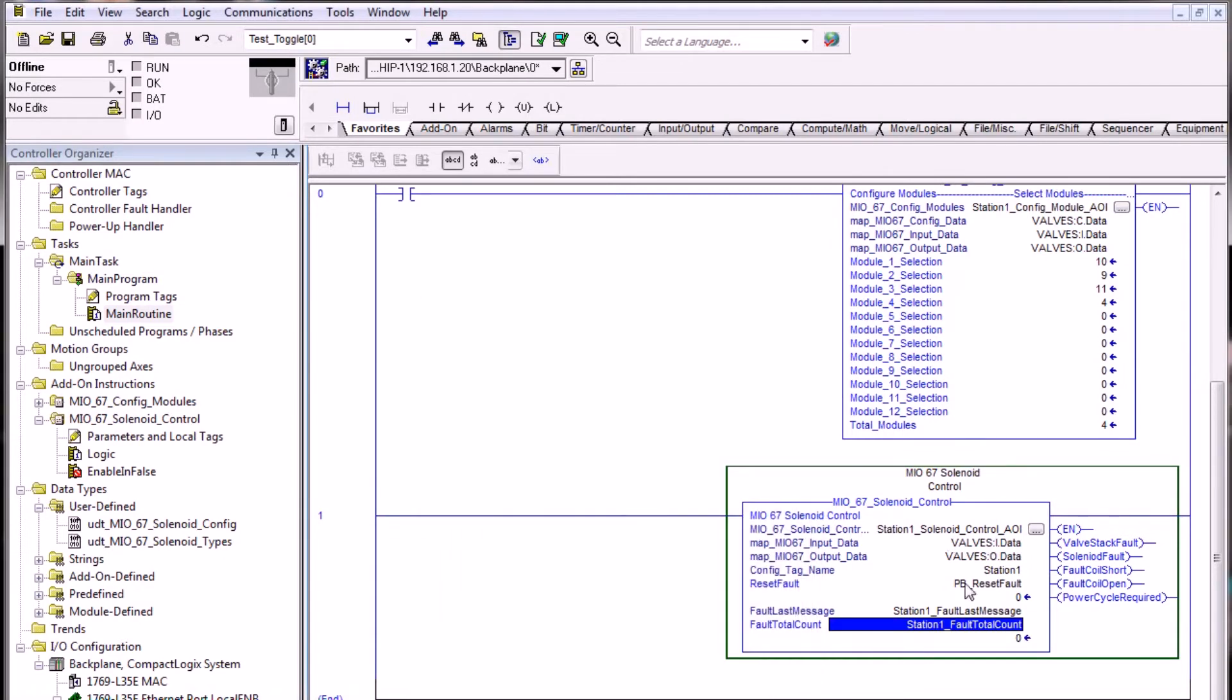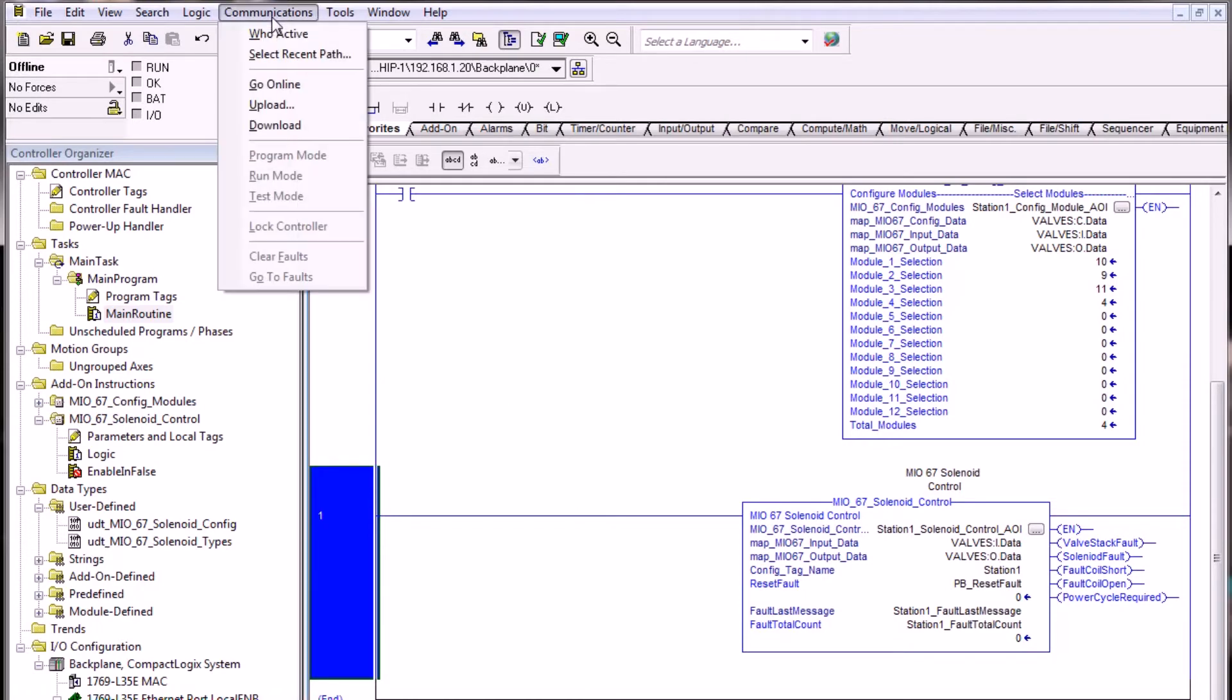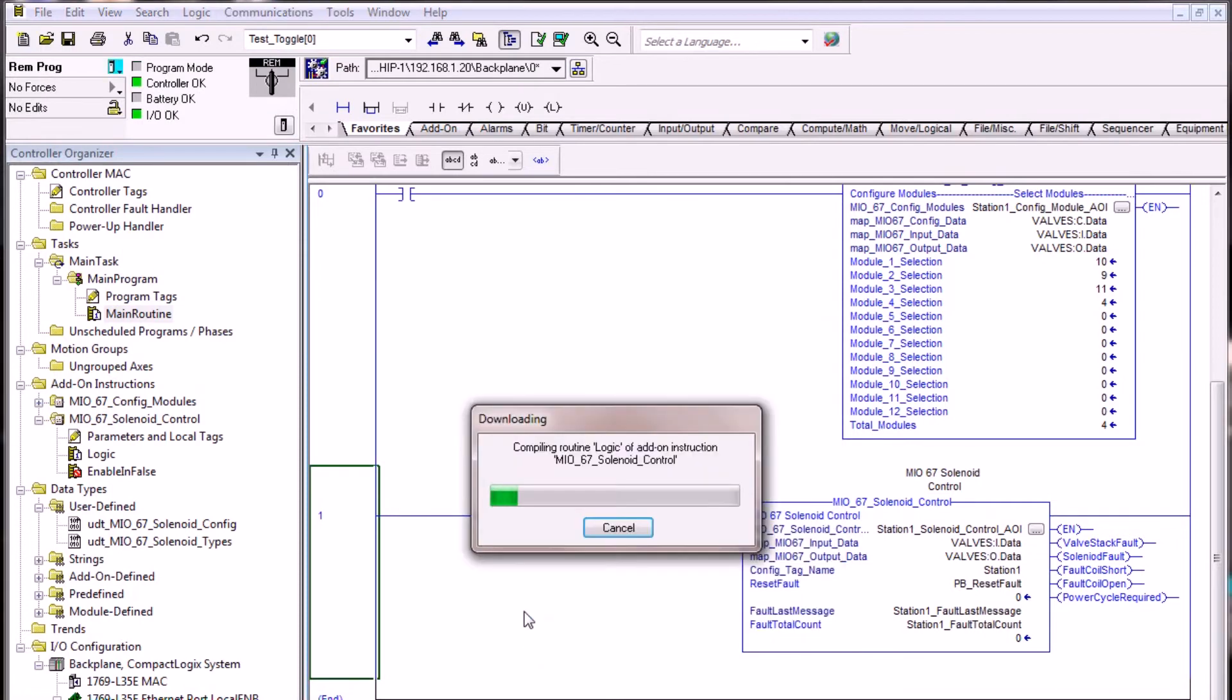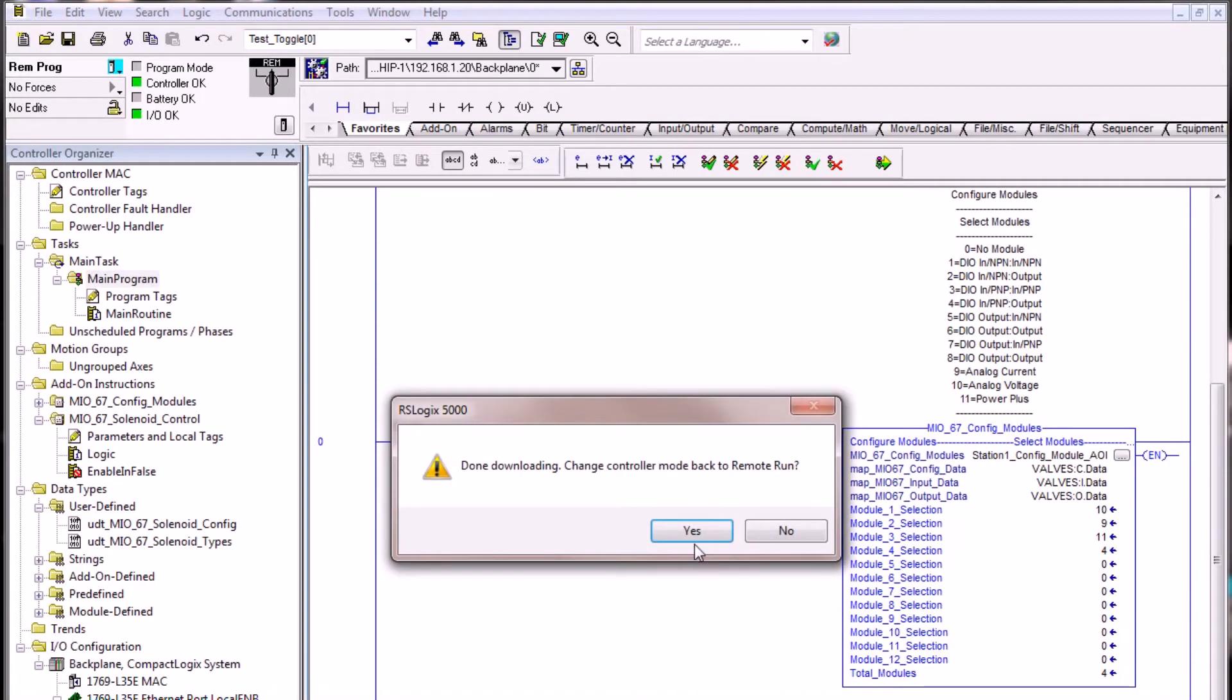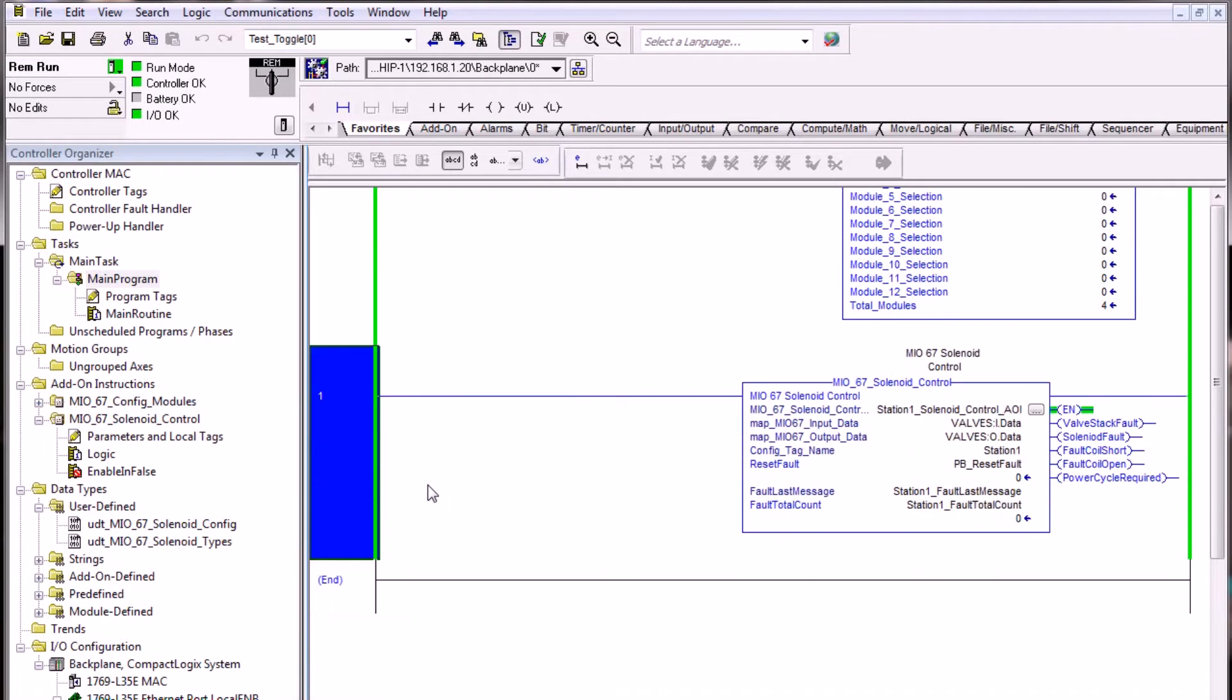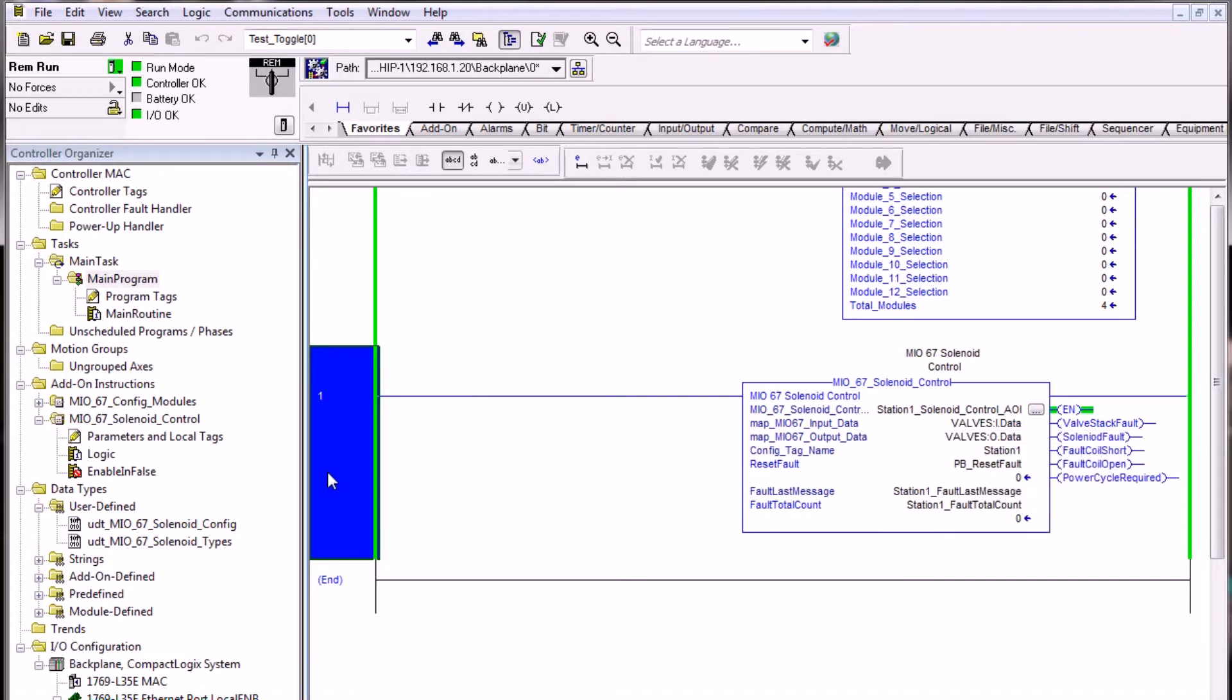Once we've created all of the input parameters, the rung is no longer an error and we may now attempt to download it into the PLC. Let's go ahead and do that now by selecting communication and download. You'll notice we do not have any kind of instruction in front of this AOI. The solenoid control AOI is meant to run continuously on a rung that does not have any kind of instruction interruption in front of it. This AOI runs continuously and monitors the valve stack and reports any valve stack faults or statuses continuously while your ladder logic is executing.